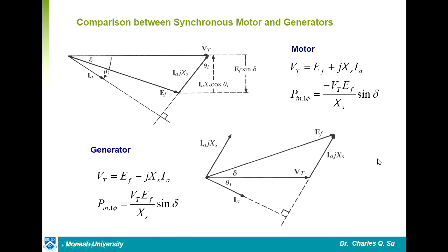If you have a generator, you have more or less the same story, only in the opposite way. The generator will drive the rotor, you produce back EMF, and you supply power. Then you have a very similar equation, except your power output is positive. Your generator supplies power, that's the positive. Again, because your terminal voltage is constant and your reactance is constant, your output power depends on back EMF and torque angle. Another thing is, with different back EMF, you would have different current. The torque angle can change, and your current would also change.